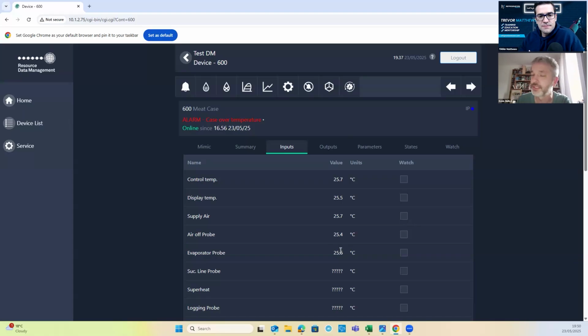I know the evaporator probe is on the inlet to the coil. I know it's going to get the coldest straight away. I know the air off probe is probably going to be the next one to get cold. And depending on where the defrost probe is, maybe the defrost probe just between the two. Supply air, I'm going to expect to be the last one to get cold, really. If that isn't happening in the order I'm expecting it, I think I'm going to have a problem on one of my probes and I'm going to be going in and chasing what's going on.